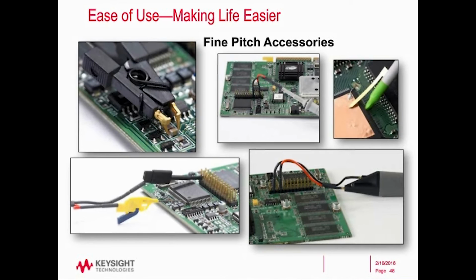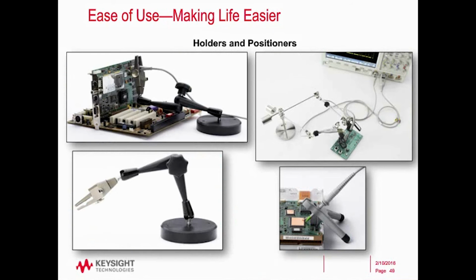So I can just clip it onto there, have my probe attached, and then I can go off and drive the scope. I don't actually have to hold the probe in place there. And in talking about not having to hold the probe in place, there's also some positioners out there. A lot of people don't know about these.